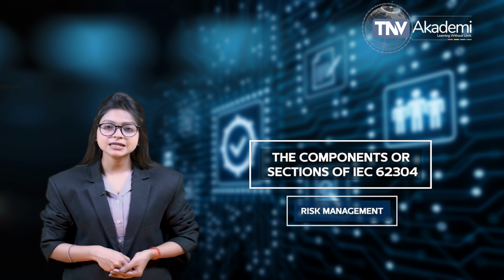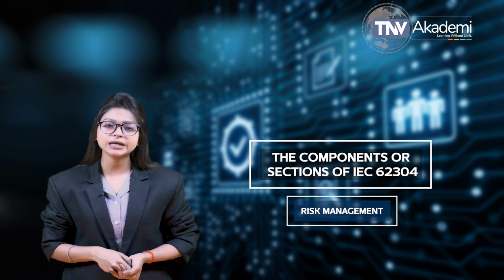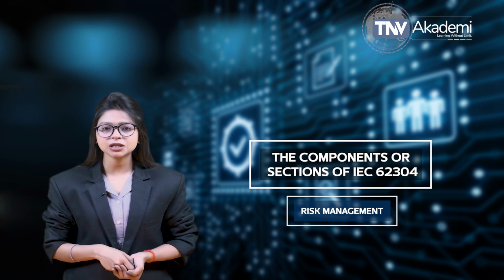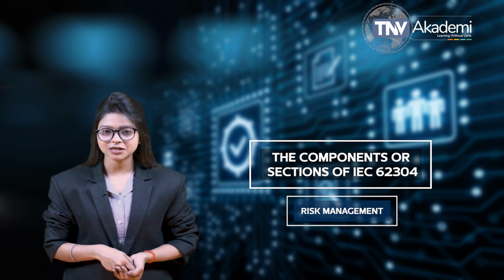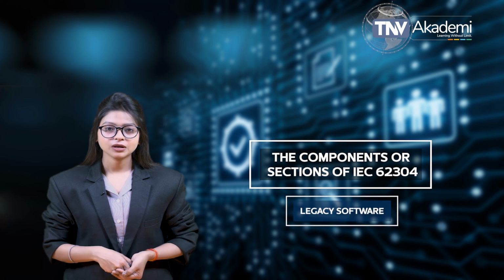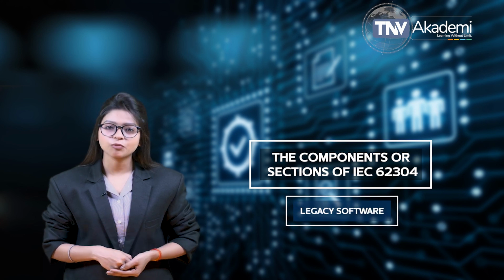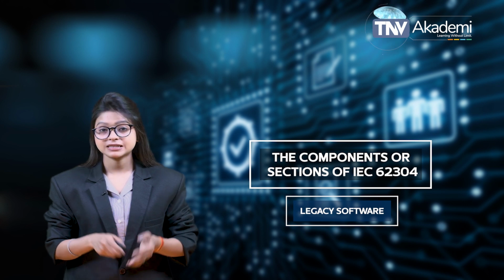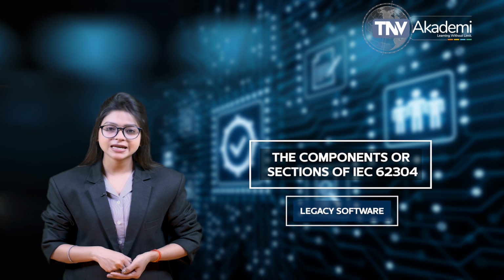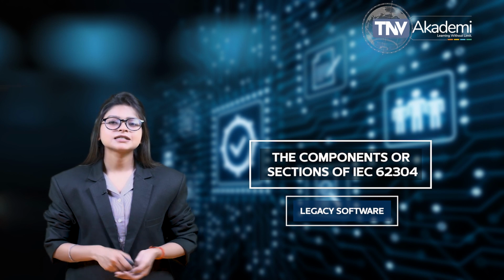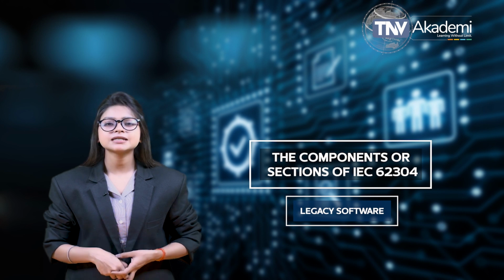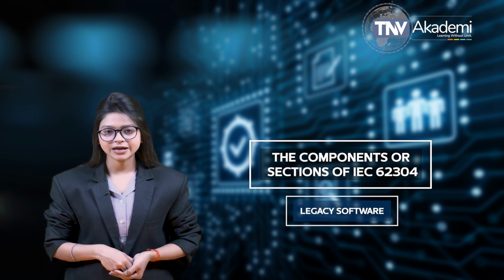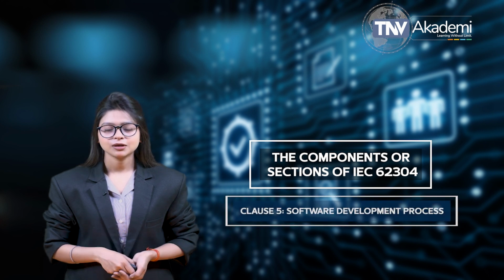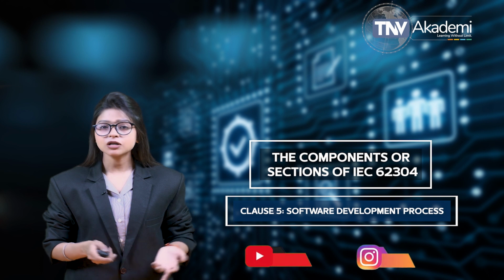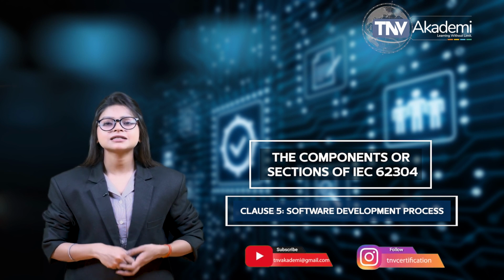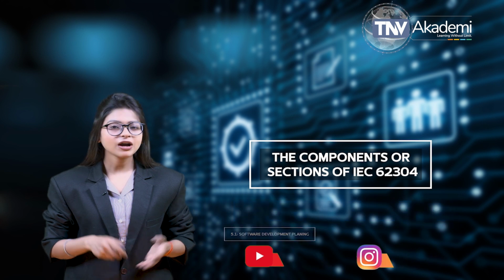Risk management: IEC 62304 requires manufacturers to be in compliance with the standard for risk management, ISO 14971-2019. Legacy software: IEC 62304 subclause 4.4 outlines the steps a manufacturer must take if choosing to incorporate legacy software into the medical device. These steps include risk management activities, gap analysis, gap closure, and rationale for use of legacy software. Clause 5, software development process. Clause 5 is the core of the standard and consists of the following subclauses. 5.1.